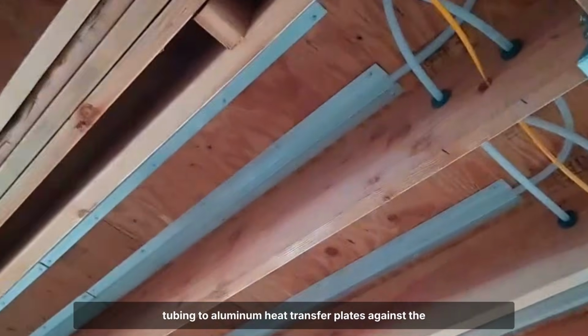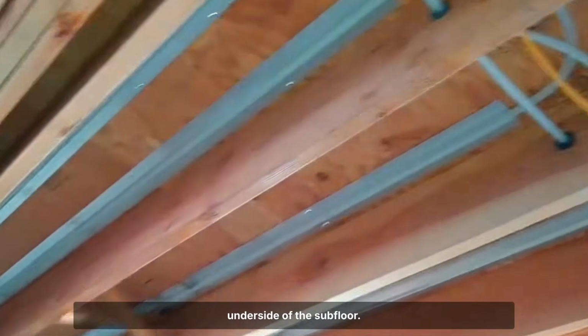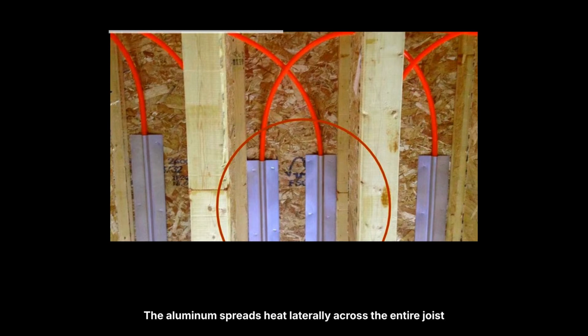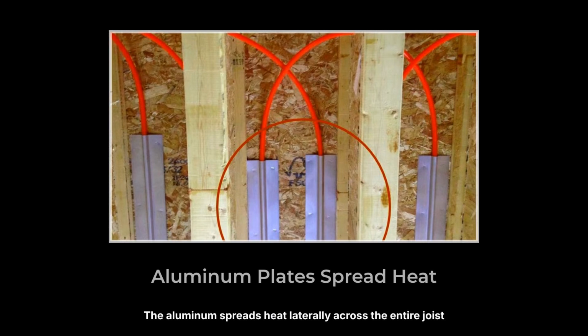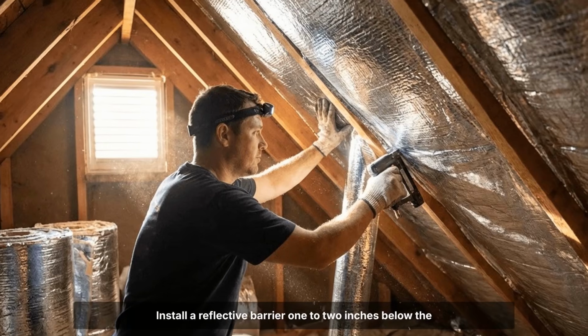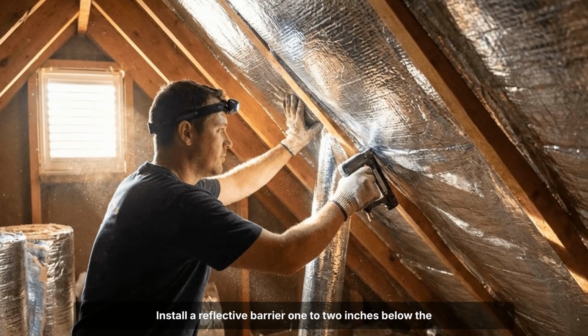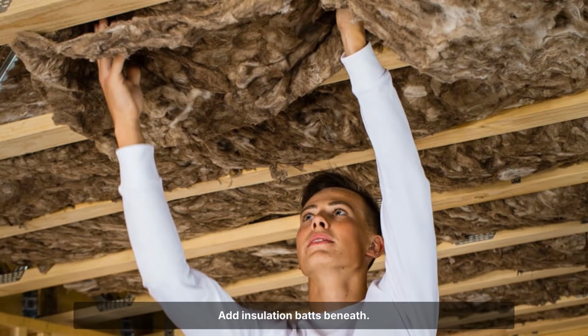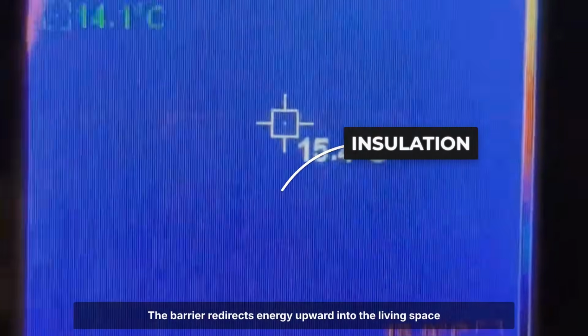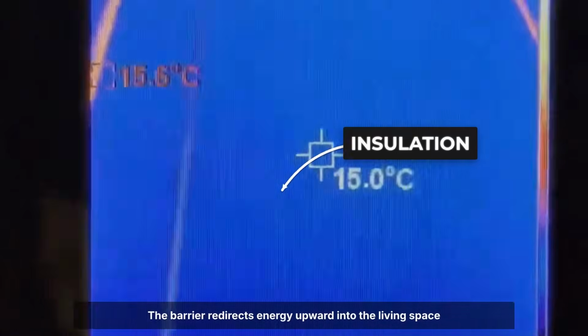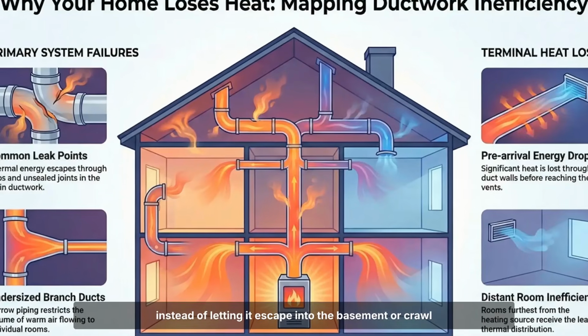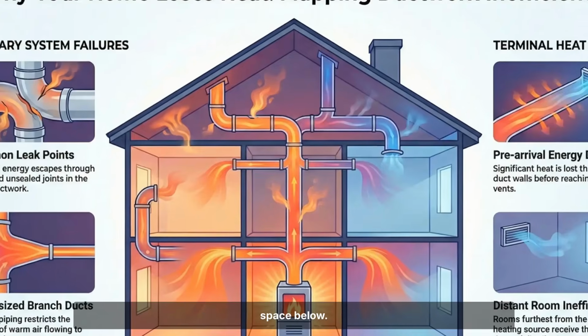For existing homes with accessible joists, attach PEX tubing to aluminum heat transfer plates against the underside of the subfloor. The aluminum spreads heat laterally across the entire joist bay. Install a reflective barrier 1 to 2 inches below the plates. Add insulation batts beneath. The barrier redirects energy upward into the living space instead of letting it escape into the basement or crawl space below.